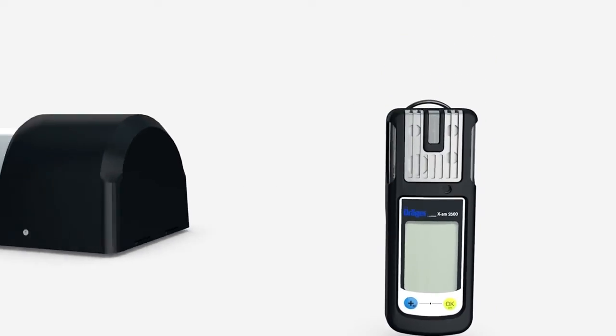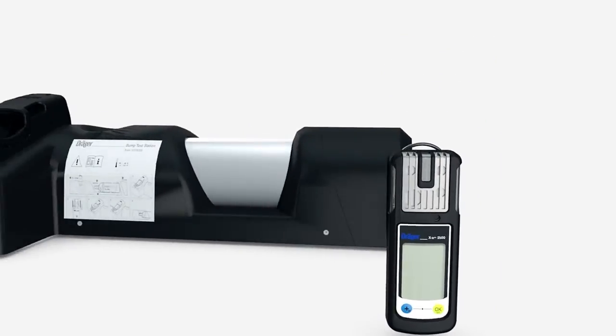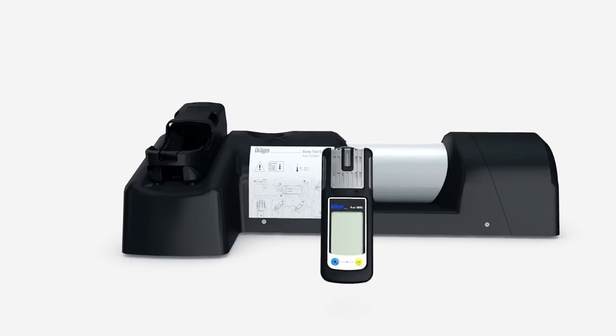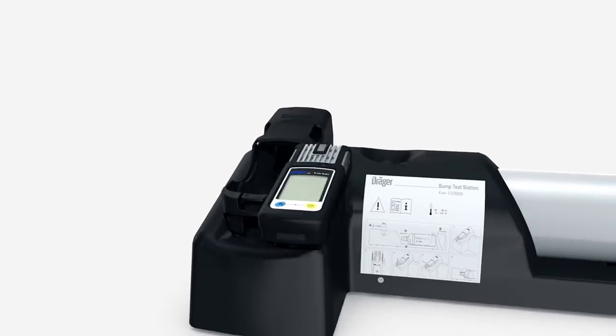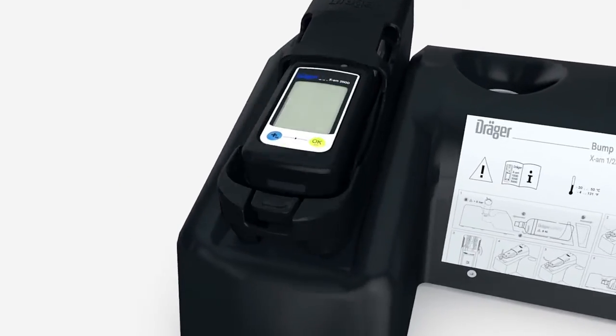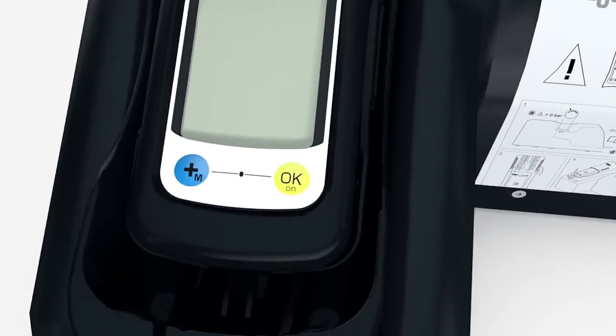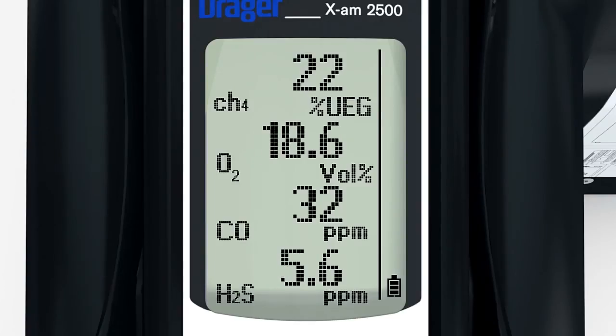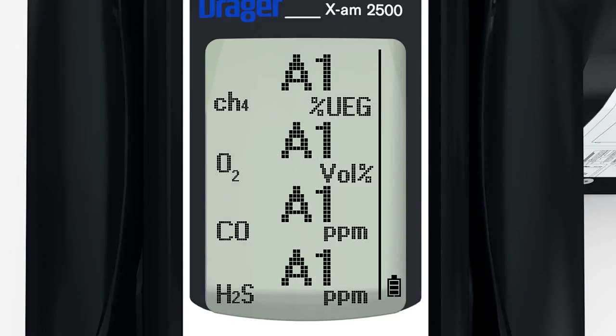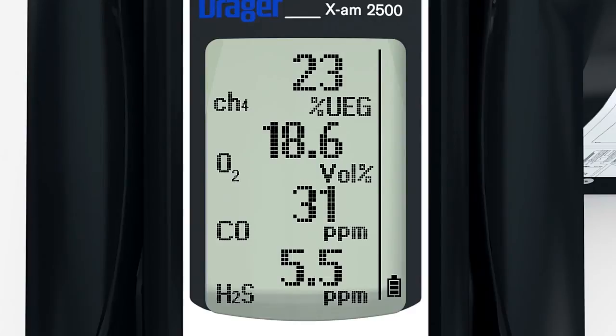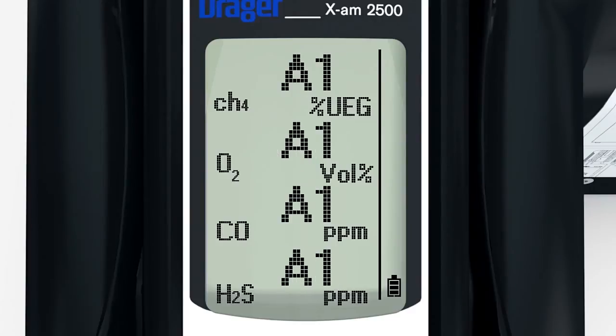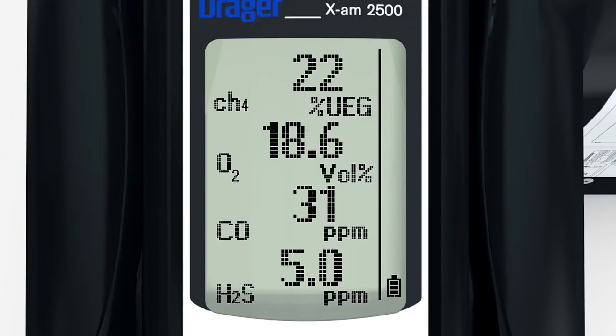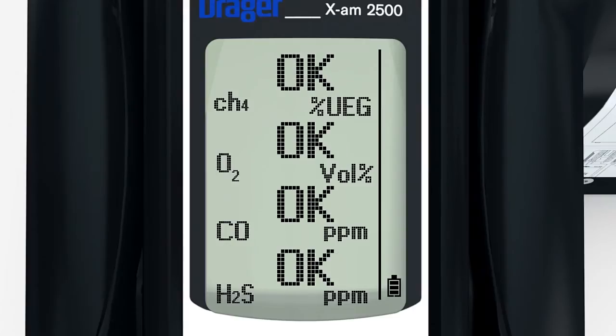Place the switched-on instrument inside the calibration cradle, where it will be recognized automatically. Gas now flows automatically over the sensors and the alarms are shown. If the bump test passes, OK will flash in the display to show that the bump test is now complete.